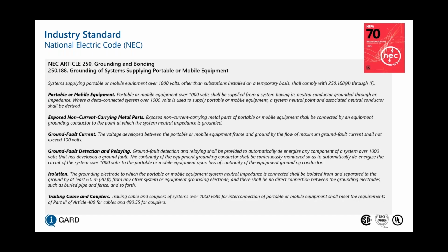For the National Electrical Code in Article 250, grounding and bonding, 250.188 indicates for grounding of systems supplying portable or mobile equipment that systems supplying these types of equipment over 1,000 volts, other than substations installed on a temporary basis, shall comply with 250.188 A through F. So portable and mobile equipment over 1,000 volts shall be supplied from a system having its neutral conductor grounded through an impedance. So that's like an impedance grounded system or resistance grounding.